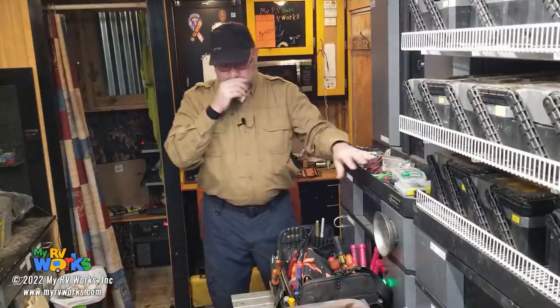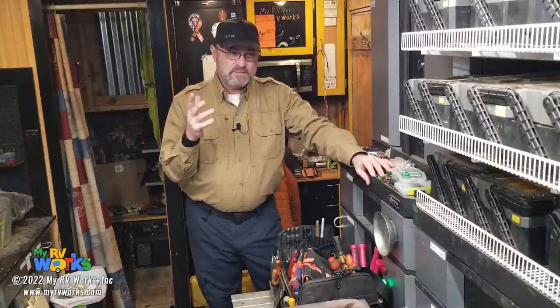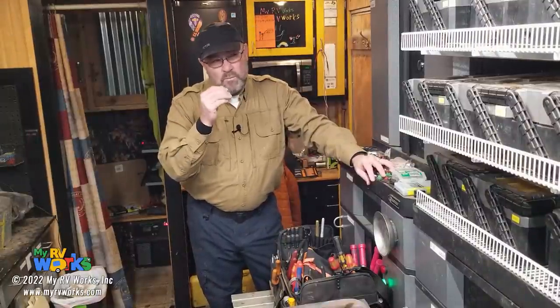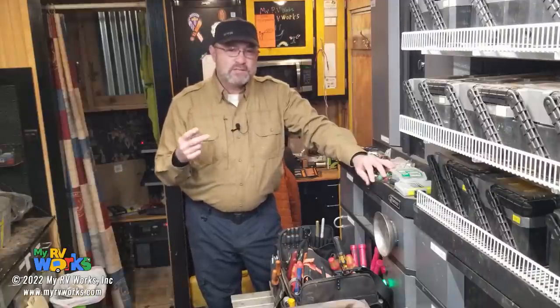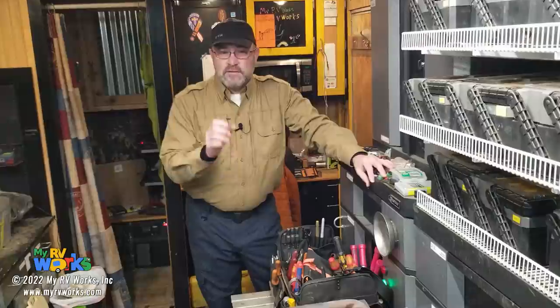So then the other thing that could be, I said there were three things. The first thing and the most obvious thing, which is why I'm spending time on this, is that high temperature switch, okay? Predominantly, that's the issue. There's two other things that could cause this cycling. One's a control board, and the other is the electrode.